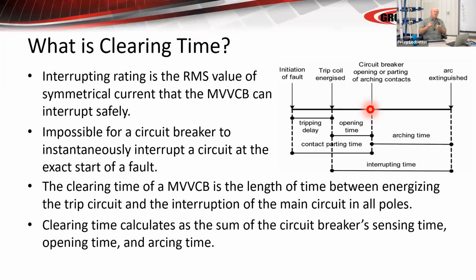And at that point, you need to either change your lubricant, increase your lubricant, or decrease your maintenance interval. The parting time, the operating time, this is the clearing time. All the way across is the clearing time, because that's the time it takes to send a signal, please open, we've got a problem, for the trip latch to drop, or for the solenoid to begin to be energized, then for the contacts to part.